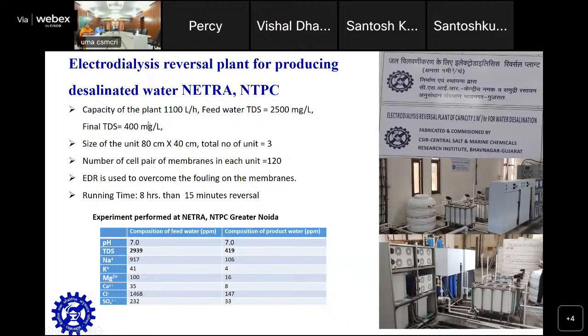Actually, they run the unit 8 hours per day, and we have installed an electrodialysis reversal switch, which is started at the beginning of the plant run for 15 minutes. Since the wastewater contains a huge amount of bivalent calcium, magnesium and sulfate ions, scale formation occurs. So we don't need to clean the membrane by opening the unit. After running the switch for 3 minutes, the polarity is changed. Cathode is changed to anode, and anode is changed to cathode. Then we throw away the water, and the membrane is cleaned automatically. Then they start running the unit and collect the water for 8 hours.